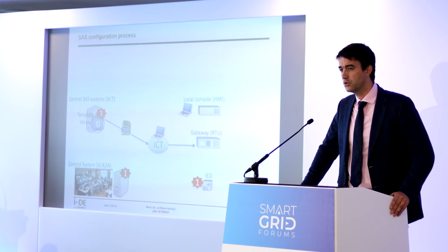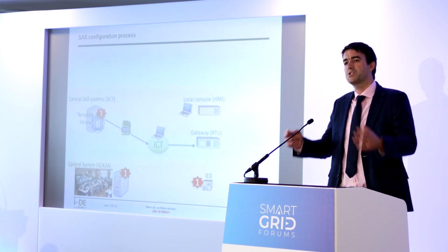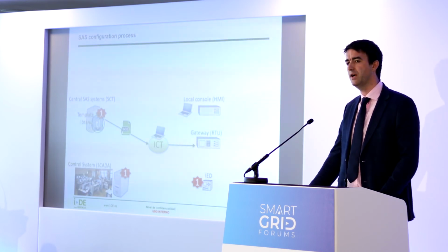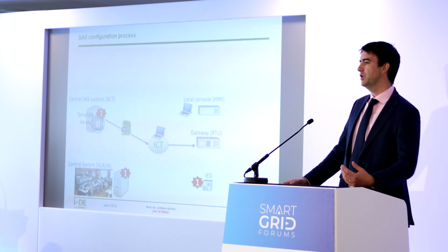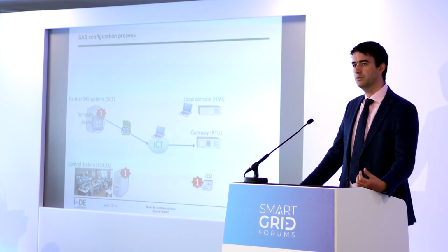This means, for example, that we can be confident that a configuration file uploaded by the system integrator during the FAT test is the same configuration file as the one which has reached commissioning during the SAT tests. This is the guarantee that can allow us to reduce the quantity of SAT testing we will have to do. Iberdrola isn't so much specifying this as recognizing something IED manufacturers can already deliver, called an IP comparison check.